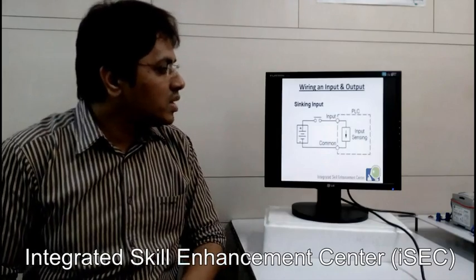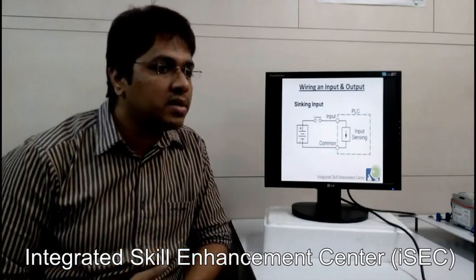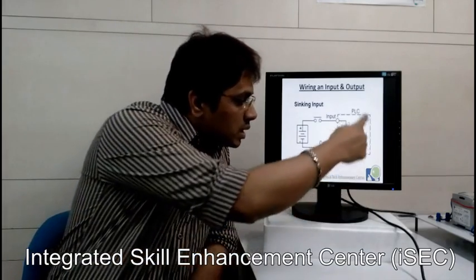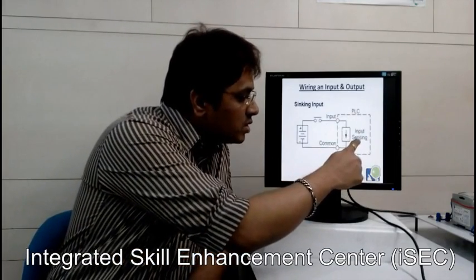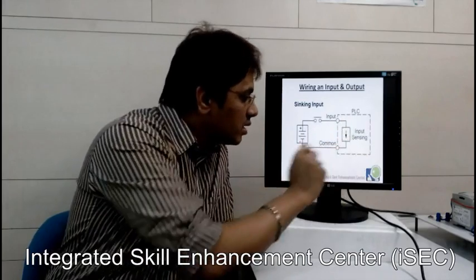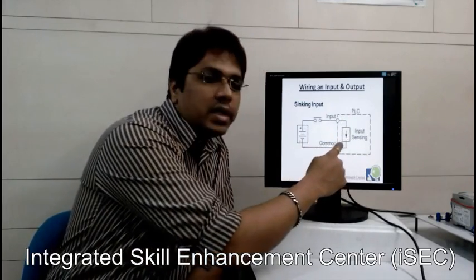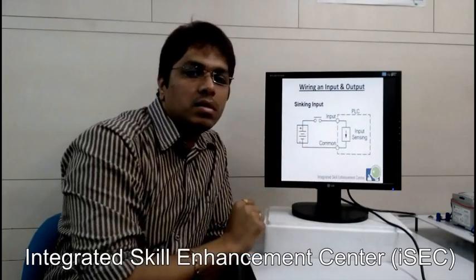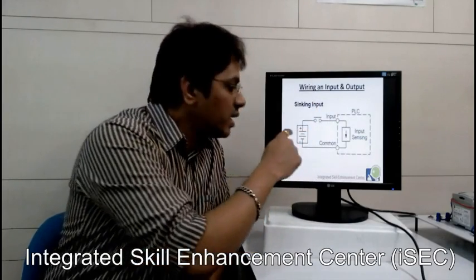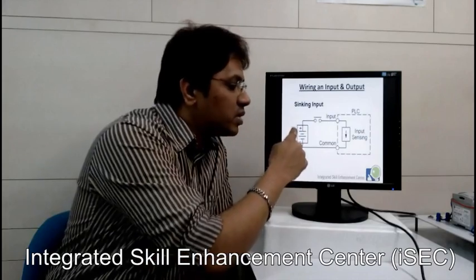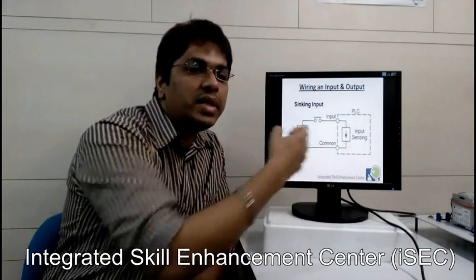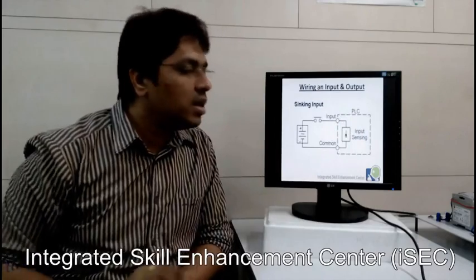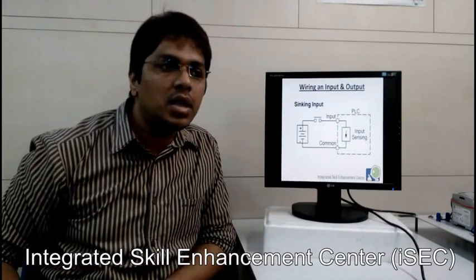Now we will see what is sinking input and how to wire it. In sinking input mode, this is a PLC. The input is sinking, so the common should be connected to the ground. You have to provide external VCC — the current goes from the power supply and the PLC takes the current. So the PLC is wired in a sinking input manner.